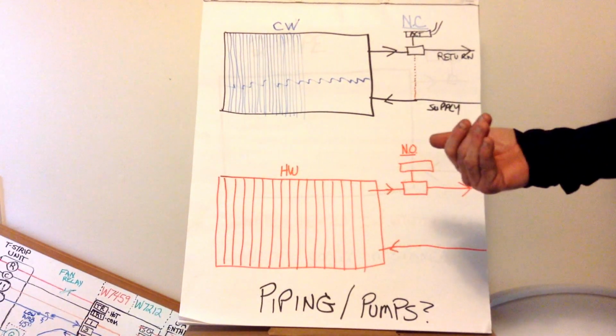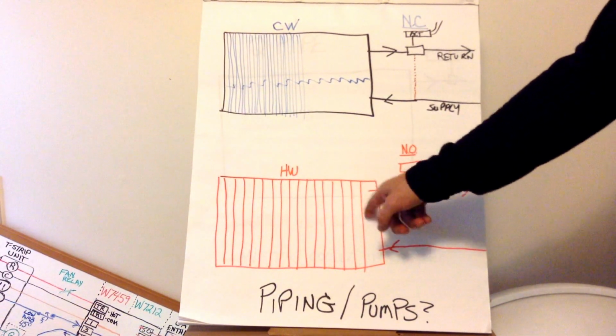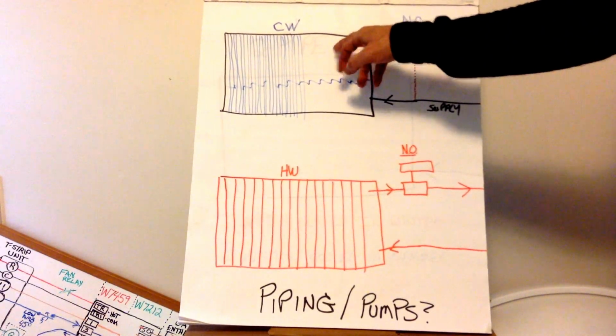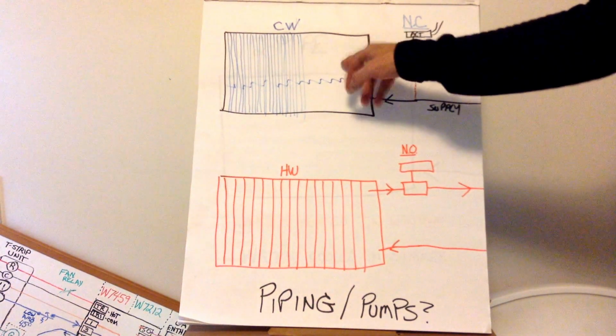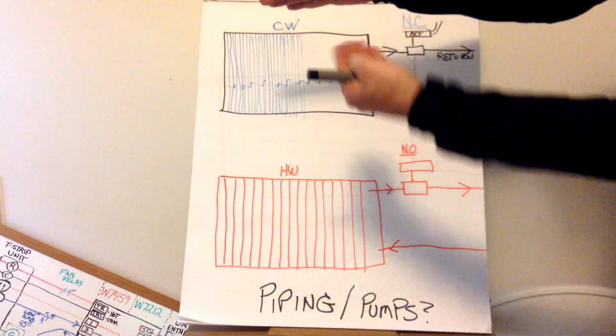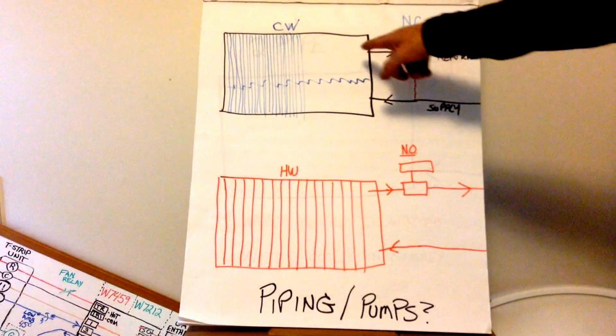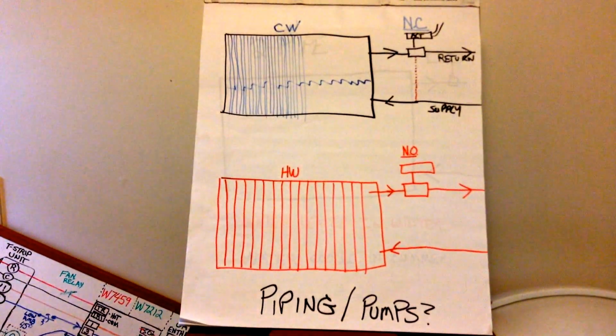The other thing you have to pay attention to is because there's a bigger gap here, the air goes past this coil. This coil doesn't get dirty. So you might look in here and say, hey, these coils are clean, I don't need to wash them. All the dirt's going to be sitting packed onto this coil. So you have to open up sheet metal. You might have to cut a hole, remove panels. You've got to look at and clean the space. If you had these two coils sitting like this, you can get in there and see that. A lot of times I see that second coil, just like a condenser coil when you got to split and wash them, this coil will have all the crap on it. And that will kill your airflow, kill your cooling, obviously. So enough on that.